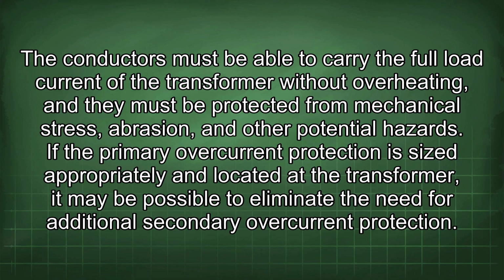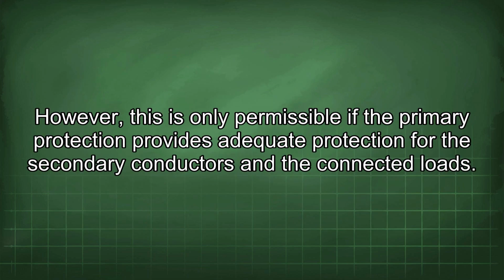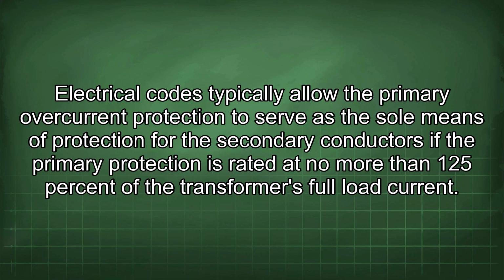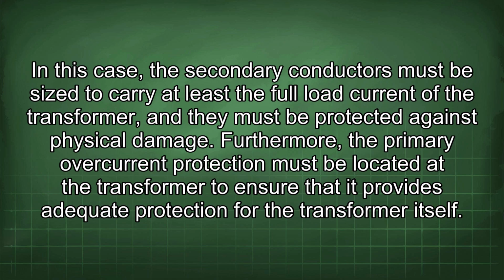If the primary overcurrent protection is sized appropriately and located at the transformer, it may be possible to eliminate the need for additional secondary overcurrent protection. However, this is only permissible if the primary protection provides adequate protection for the secondary conductors and the connected loads. Electrical codes typically allow the primary overcurrent protection to serve as the sole means of protection for the secondary conductors if the primary protection is rated at no more than 125% of the transformer's full load current. In this case, the secondary conductors must be sized to carry at least the full load current of the transformer, and they must be protected against physical damage. Furthermore, the primary overcurrent protection must be located at the transformer to ensure that it provides adequate protection for the transformer itself.